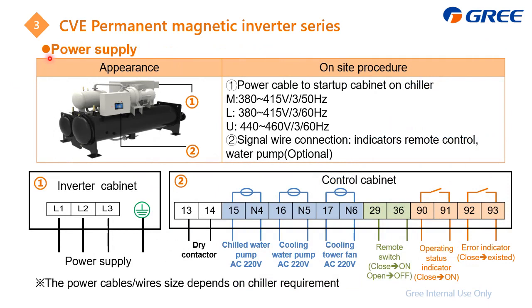Next is the power supply. According to the centrifugal chiller, which is low voltage and high voltage, we divide it into different types. This case is just to display the low voltage. You can also identify from here. Number 1 is the power cable for the 3 phases. This is still low voltage, just consider it is the centrifugal chiller. Number 2 is for the external wiring, where you need to connect to the chilled water pump or the cooling water pump, and also the cooling tower fans. This is also the remote switch to turn on or turn off, and the operating status and error indicator.